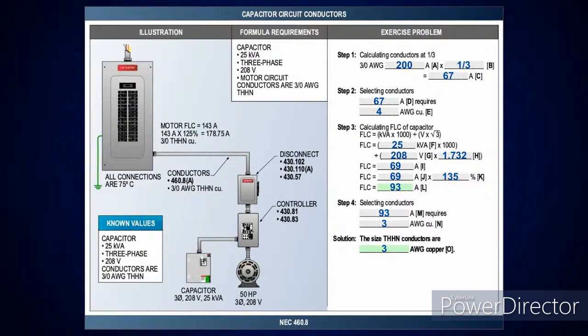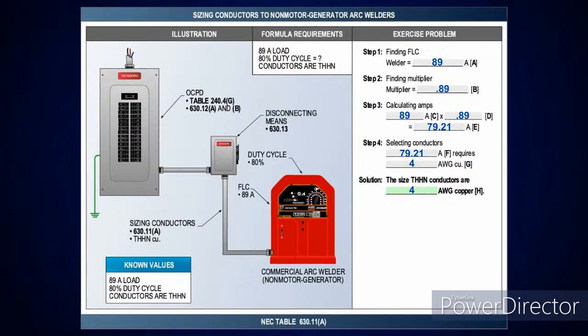Now, as I go in and I look at welders, this is very simple. All you need to keep in mind here is you need to go get the multiplier. Okay. Well, we're going to give you some known values here. You got 89 amps of load and you got 80% duty cycle. Okay. And we're going to size THHN. Now, the welder's 89 amps. And then if I go look at the duty cycle for 80%, it's going to tell you that the multiplier is 0.89. So I'll just take 89 amps times 0.89, going to give me 79, and I'll look at 310.16, 75 degrees C column. The next size above that's a number 4, which is good for 85 amps.